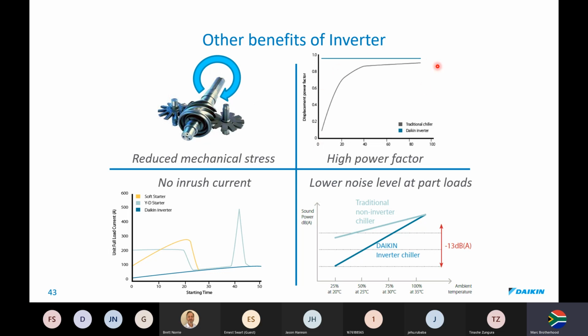So let's say you've got a factory, each time you start the chiller, a normal chiller will take huge power from the transformer to create a magnetic field to get the chiller rotating, the compressor rotating. We don't need that. So our power factor runs just below 1, at around about 0.97. There's also no inrush current, which is fantastic for transformers as well as switch gears.